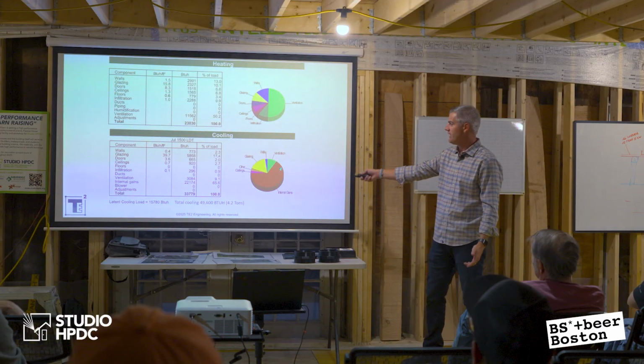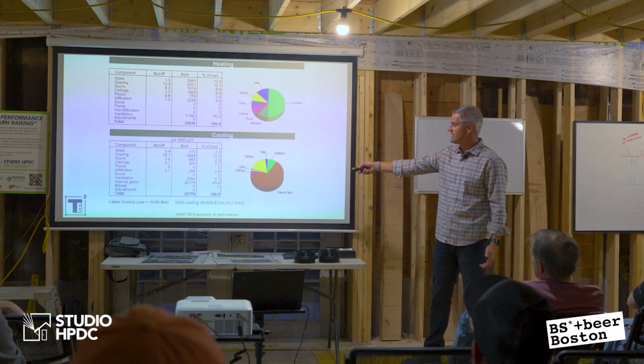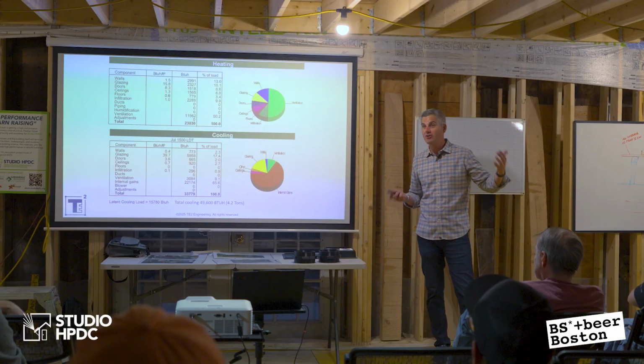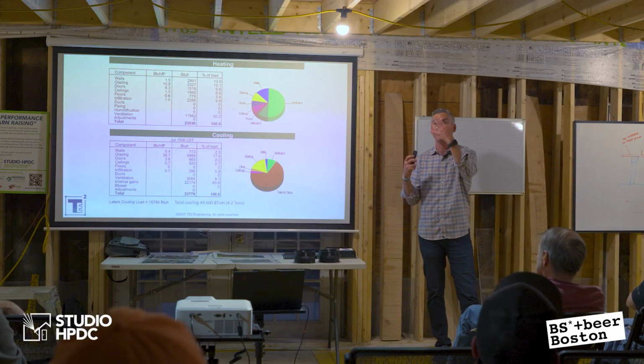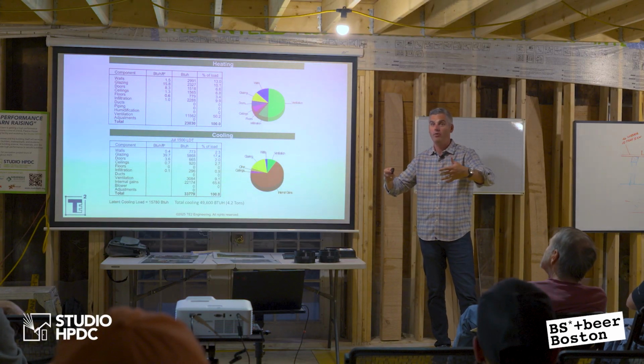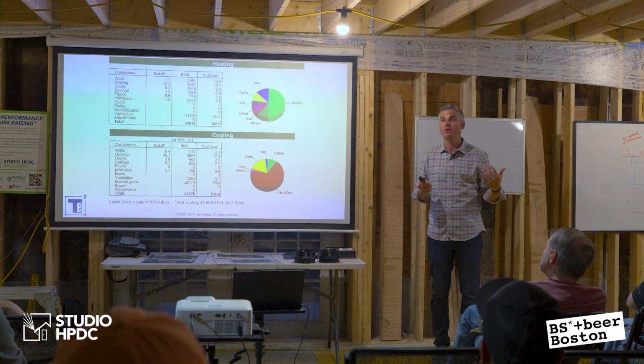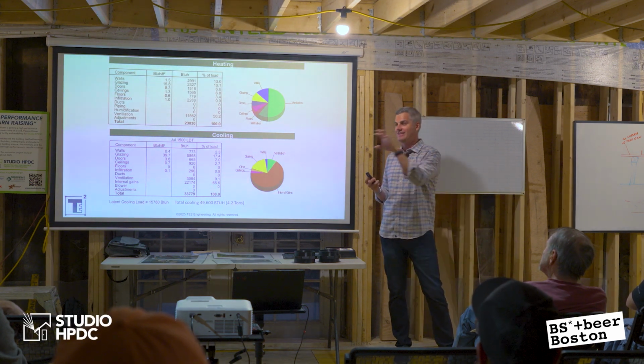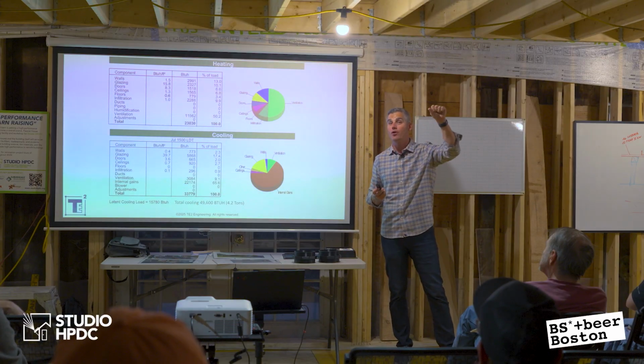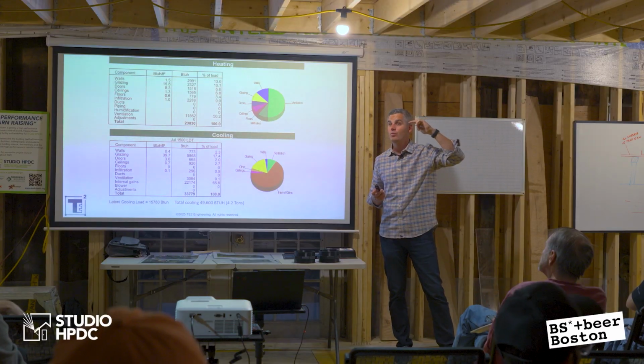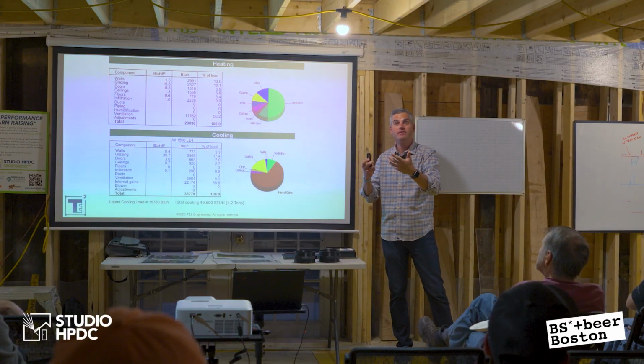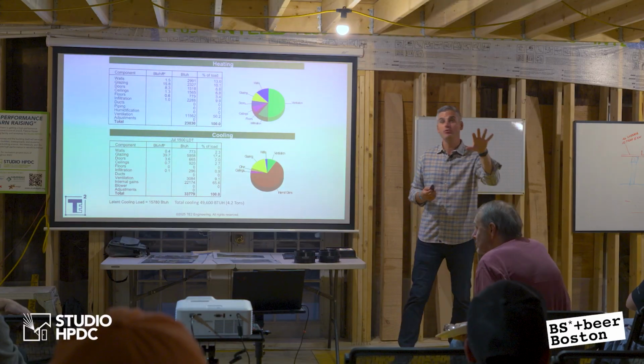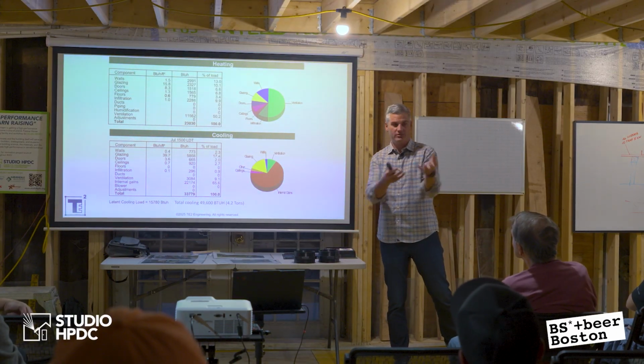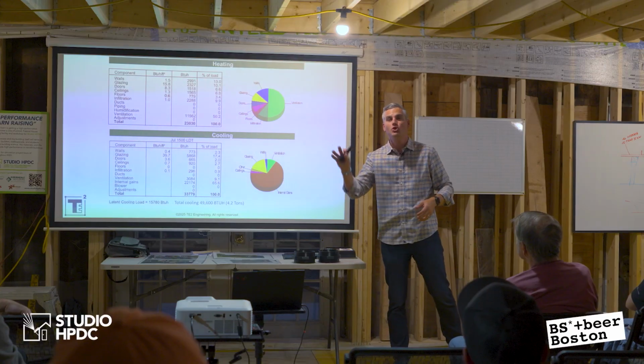Look at the cooling load, right? The ventilation, the walls, the glazing, the ceilings. Look at all the percentages. It's dominated by internal gains. And the internal gains is the 55 people that are all giving off heat because we breathe, right? We give off water vapor, right? We have latent load and we have sensible load. Each person that's sitting right now is giving off 230 BTUs per person of sensible and 200 BTUs of latent. Because we're breathing. Sensible and latent from a human is basically equal. Sensible is about 230 for a person at rest, sitting in a chair, and 230 sensible, 200 latent.